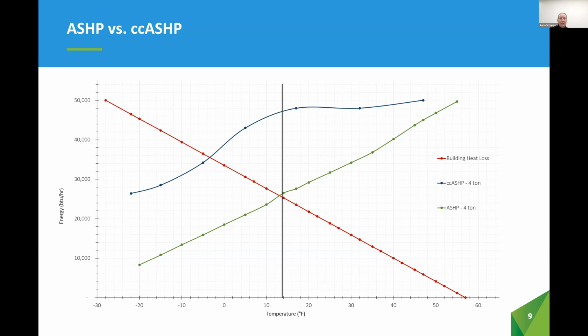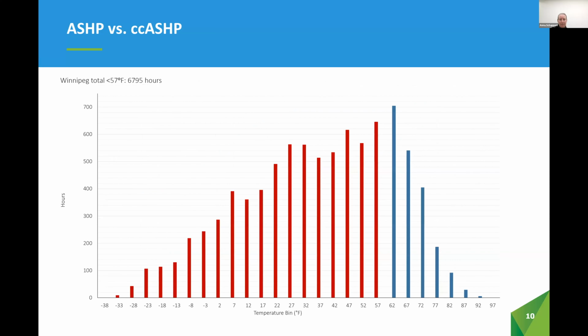The balance point of the standard air source heat pump falls at about minus 10 degrees Celsius, and the balance point of the cold climate air source heat pump falls at about minus 20 degrees Celsius. As this is a Manitoba specific session, I'll assume most of us are familiar with the winter weather that we have here. More specifically, the temperatures can sometimes go below minus 30 periodically throughout the winter.